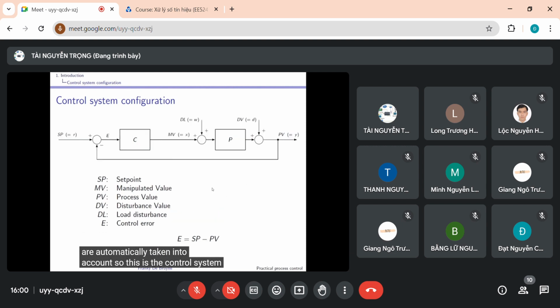So this is the control system configuration that we end up with. The process here also includes the effects coming from the actuator or the sensor. Here the controller, in our case, will very often be a PI or PID controller. SP, the set point, is the signal we want to track. PV is the output signal. Over here you see the feedback part. E is the control error, set point minus PV, and on the basis of E, the PID control algorithm will compute MV.